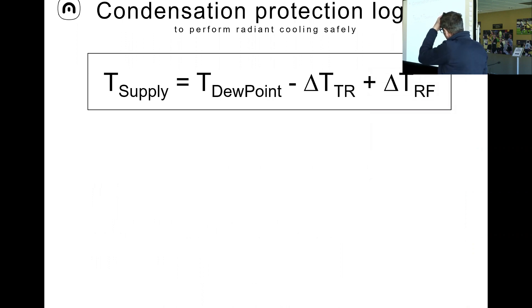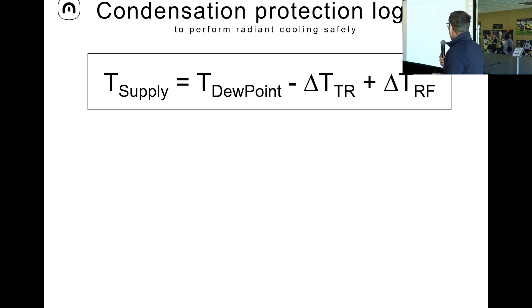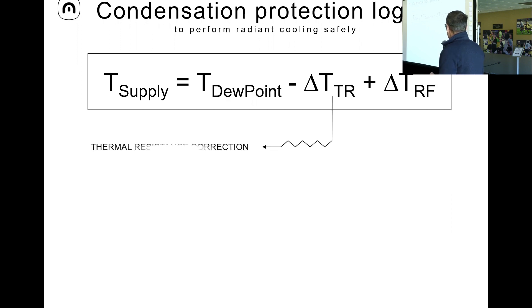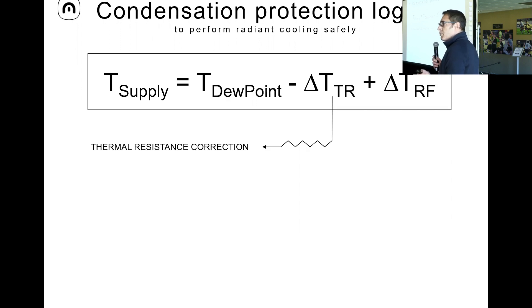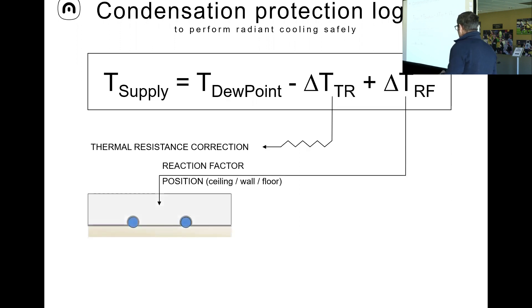Strategies for condensation protection are mandatory for radiant cooling, especially on the ceiling when you want to push performance. With a three-way valve, we adjust the supply temperature of our hydronic system. The temperature depends on the delta TR — the thermal resistance correction. The performance of a radiant cooling system really depends on the thermal mass. If this is our panel in the ceiling — the EPS, the pipes, the aluminum transfer plate, and the gypsum layer — and the dew point in the room is say 18°C.